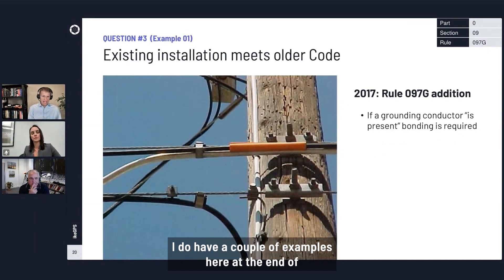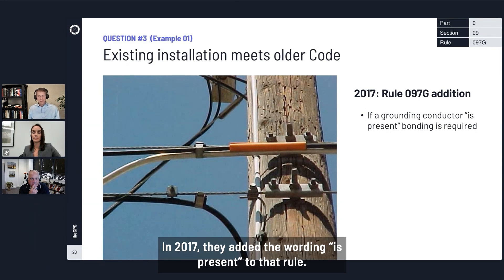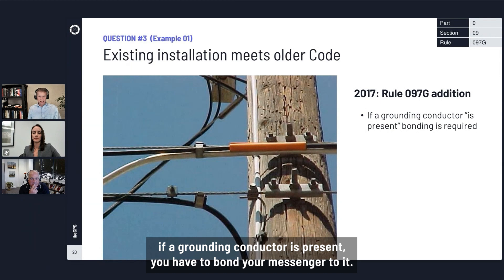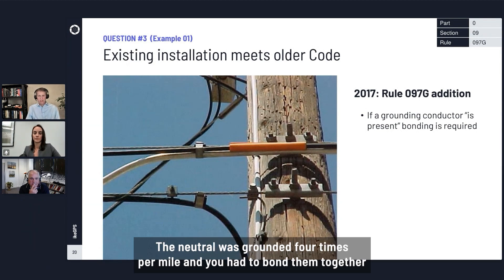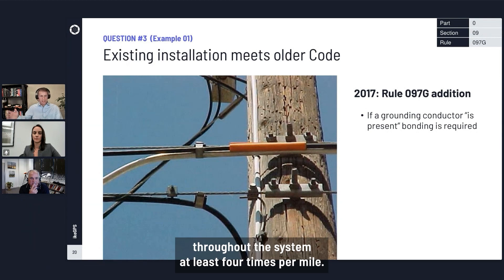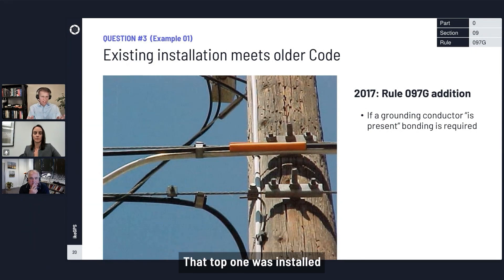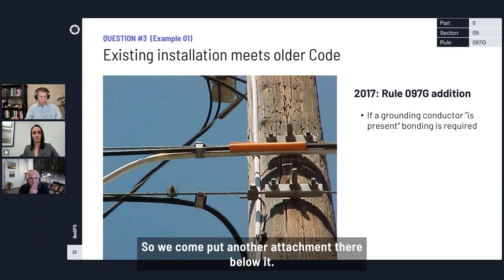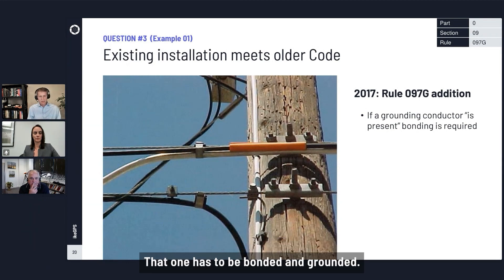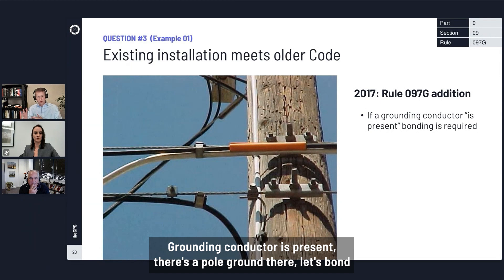Here's a first example: Rule 097g. In 2017 they added the wording 'is present' to that rule, so it now says if a grounding conductor is present, you have to bond your messenger to it. Before 2017, you had the neutral grounded four times per mile and had to bond them together throughout the system, but they didn't all have to be connected to a pole ground on the pole if it was there. If the top attachment was installed before 2017 and meeting an old edition of the code, they don't have to change it. But when we come to put a new attachment below it, that one has to be bonded and grounded — meet the 2023 code; if a grounding conductor is present, bond over to it.